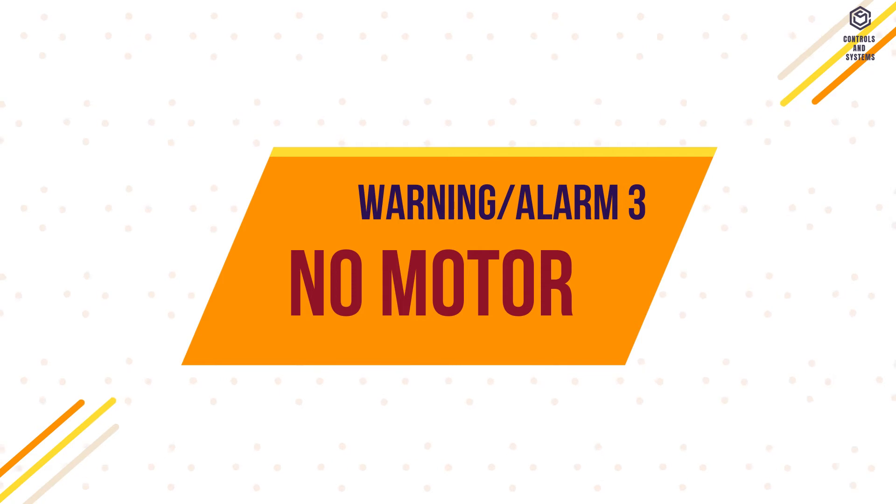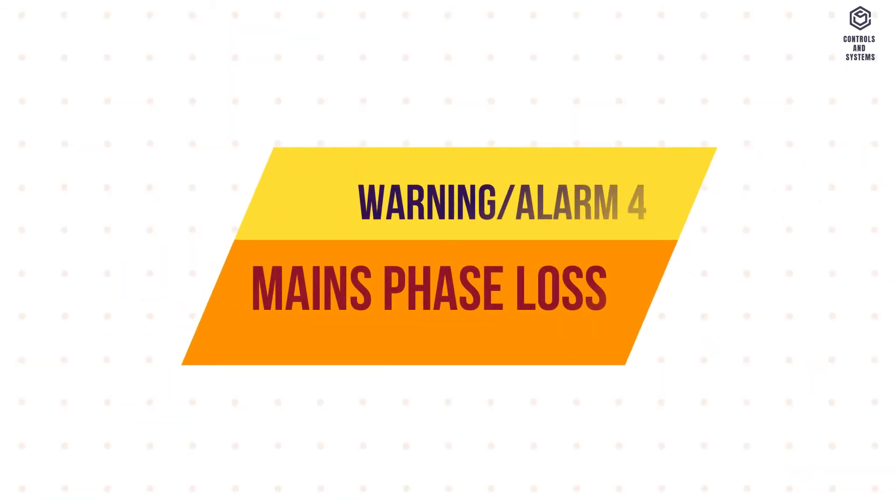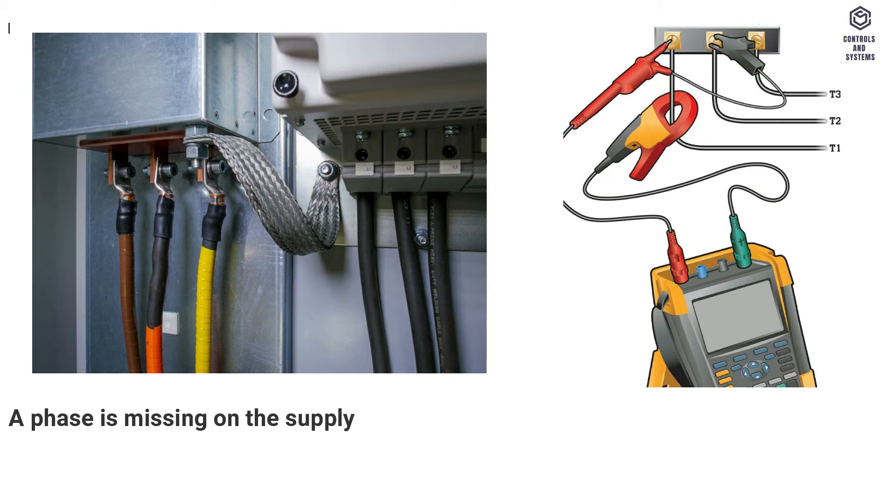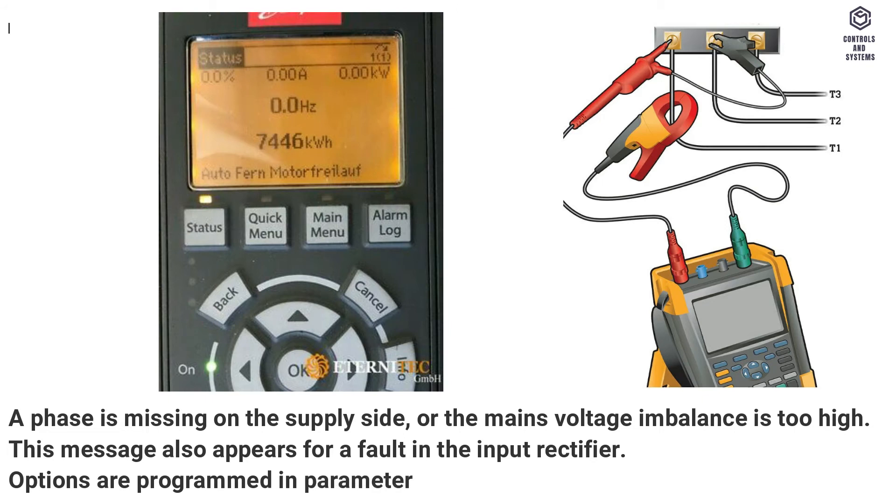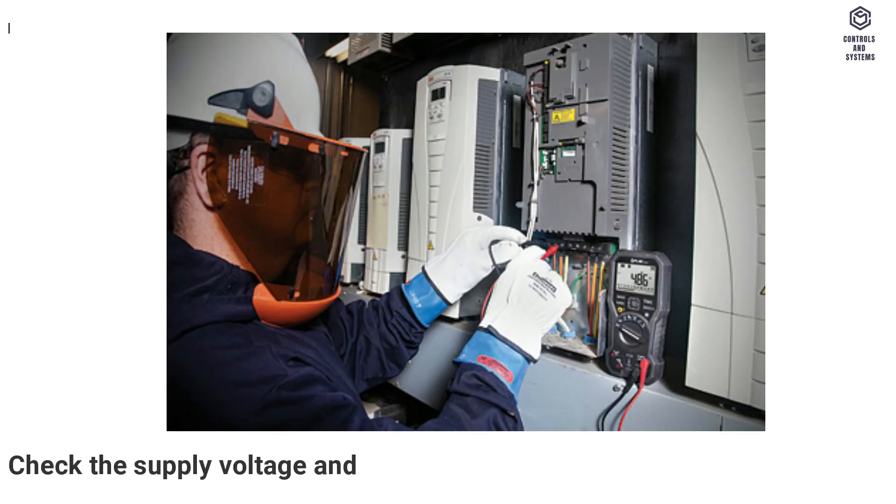Warning, Alarm 3, No Motor. No motor is connected to the output of the frequency converter. Warning, Alarm 4, Mains Phase Loss. A phase is missing on the supply side, or the mains voltage imbalance is too high. This message also appears for a fault in the input rectifier. Options are programmed in parameter 14-12 Response to Mains Imbalance. Troubleshooting methods: Check the supply voltage and supply currents to the frequency converter.